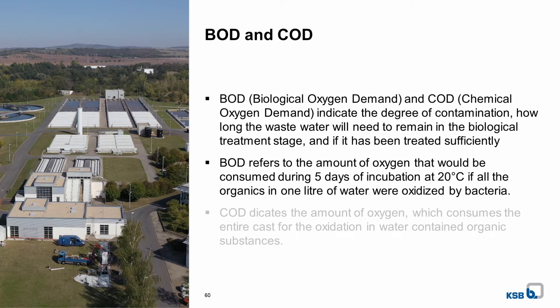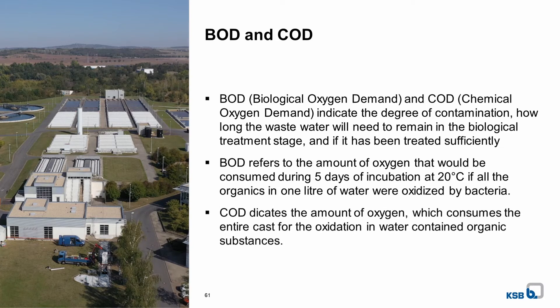We could also say: what do the bacteria need for their metabolic processes? The COD is used for direct chemical processes. It indicates the amount of oxygen needed to oxidize all organic substances contained in the water. An oxidizing agent decomposes the biodegradable and non-biodegradable substances and produces carbon dioxide. The COD is mainly used in the context of industrial wastewater treatment plants.